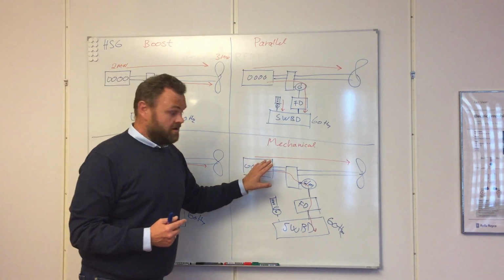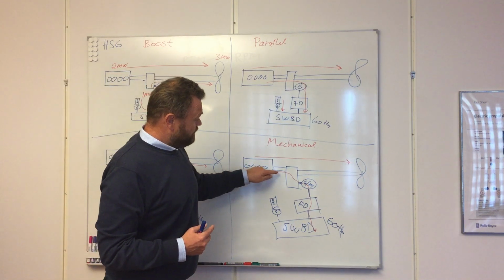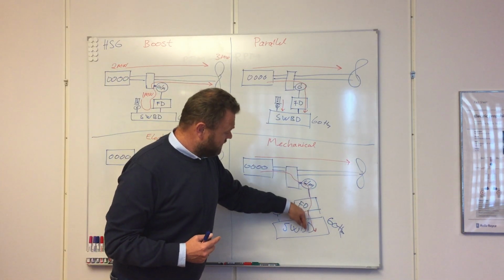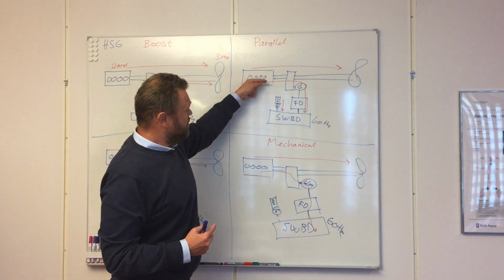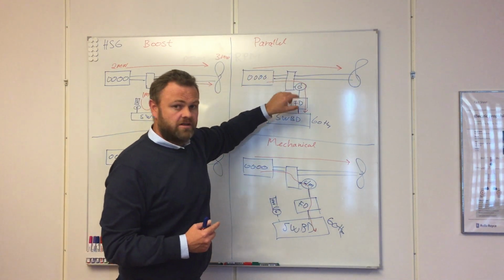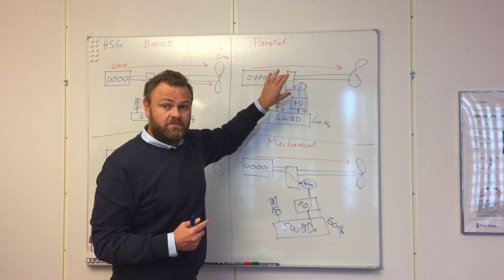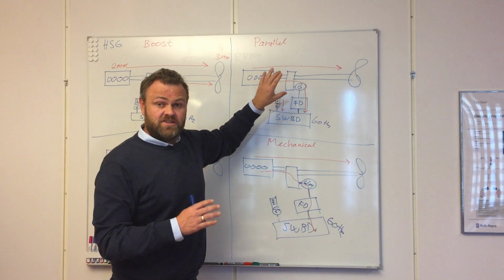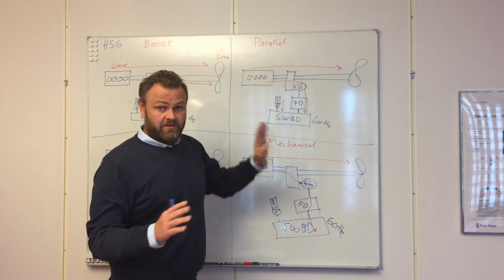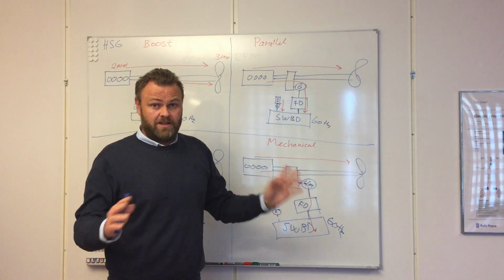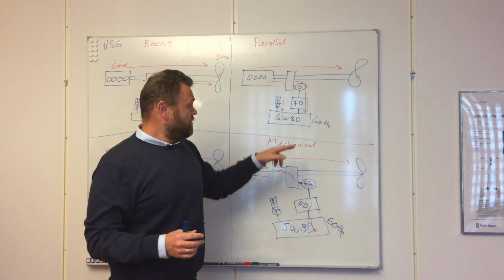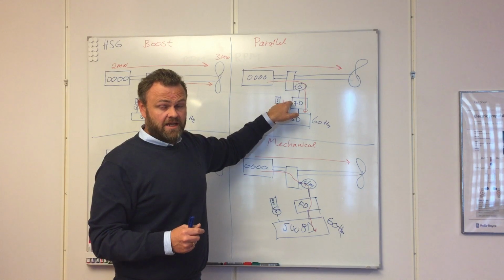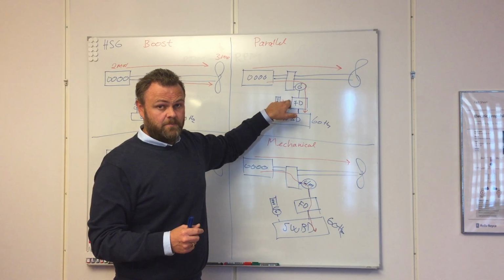But over here, the power is flowing in that direction. The power is flowing in that direction through the same frequency drive. This is not possible with a 12 pulse, 6 pulse, or 24 pulse solution. You need an active front end inside here.